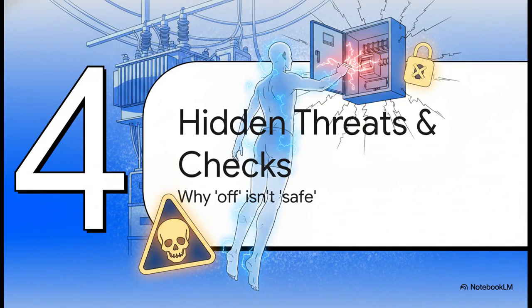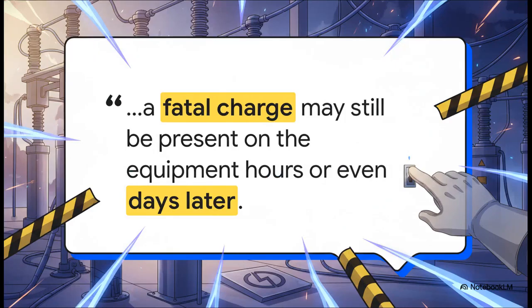This brings us to one of the most important, and frankly scariest, concepts in high-voltage safety: the hidden threats. Just because a breaker is open, that does not mean the danger is gone. Not even close. And listen to this quote, straight from a safety manual. It's chilling, but it's a fact: a fatal charge can hang around on high-voltage equipment for hours, or even days, after it's been disconnected. This is that invisible killer that makes the earthing procedure so absolutely critical.